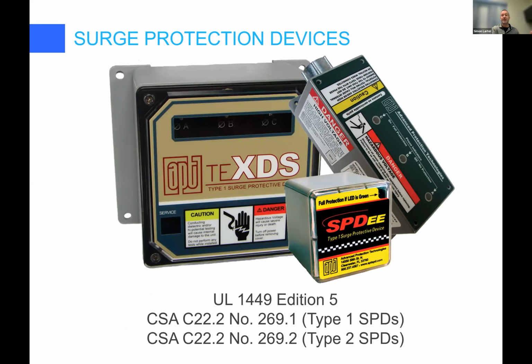You've got type 1 and type 2 SPDs. It just depends on the location. Type 1 is more for the main distribution gear. Type 2 can be put on smaller sub panels and distribution panels. But UL 1449 is edition 5. That's generally what these things are listed to. And then CSA has its own standards about type 1 and 2 SPDs.